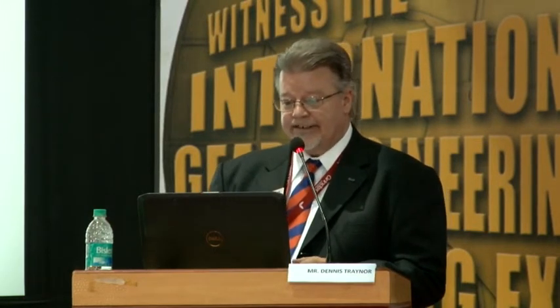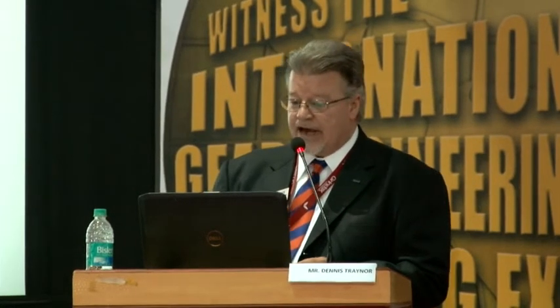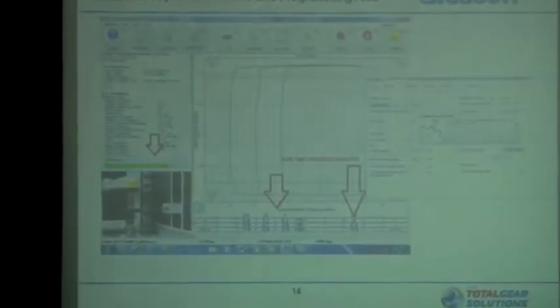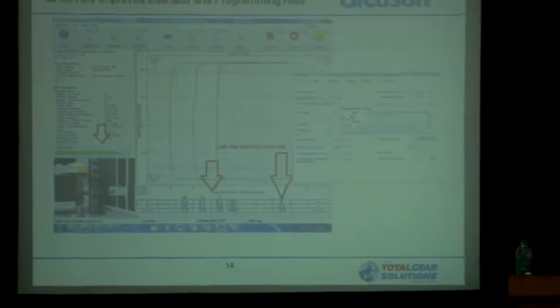This graphic is the standard operator interface as it's laid out in GAMA. Across the top, you see what we call quick buttons. Those are accessed either by a mouse click, the F buttons, or the function buttons across the top of the computer screen. They're the most commonly used functions in the program, whether it's to call up a part, start a new part, abort a part program, or calibrate a probe.